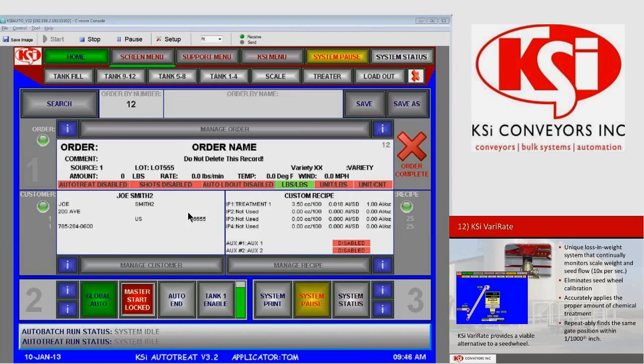For example, if on the order setup you request 2,000 pounds per minute to be delivered through the treater, when you start your system it is going to deliver from the scale 2,000 pounds per minute. However, if there is an obstruction in the scale hopper and the seed flow changes to 800 pounds per minute, the pumps will follow that and will begin applying at 800 pounds per minute as opposed to the 2,000 pounds per minute that was requested on the order.